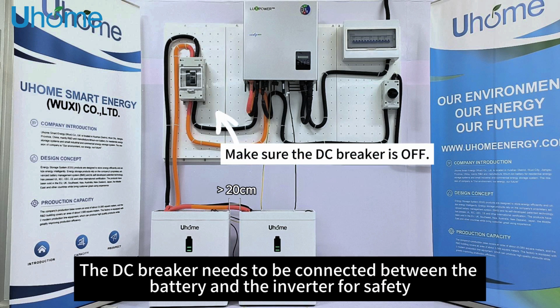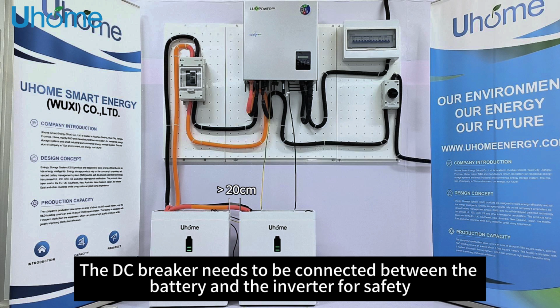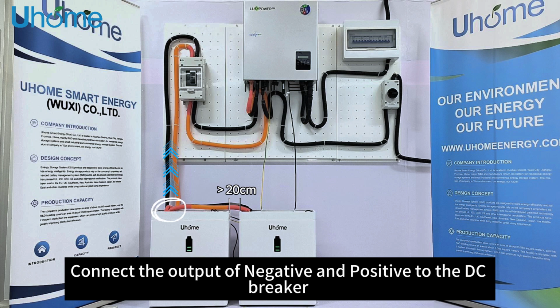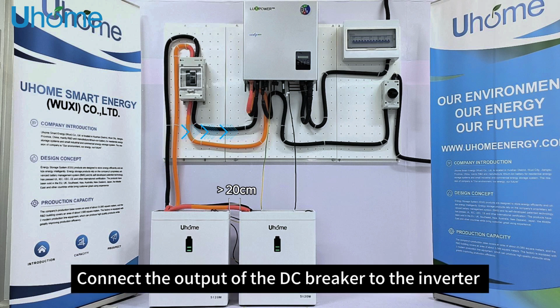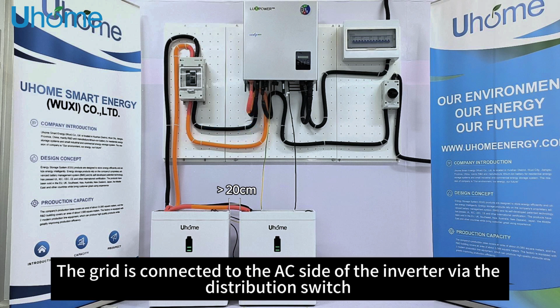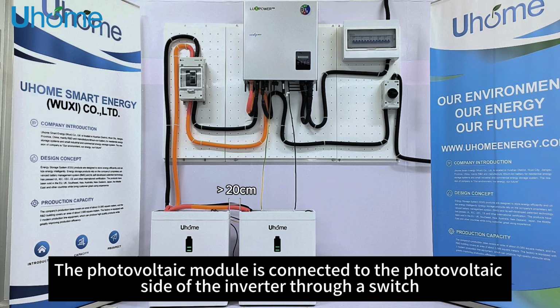The DC breaker needs to be connected between the battery and the inverter for safety. Connect the output of negative and positive to the DC breaker. Connect the output of the DC breaker to the inverter. The grid is connected to the AC side of the inverter via the distribution switch. The photovoltaic module is connected to the photovoltaic side of the inverter through a switch.